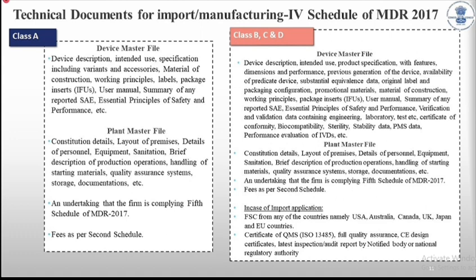It also comprises risk management documentation, design validation documentation, and the various stability testing documentation. Another part is the plant master file, which illustrates the plant conditions, the layout, the equipment, and the competency of the staff working in the plant. With this technical document, they also submit the documents on the fees and the design certificates to establish the safety, quality, and performance.